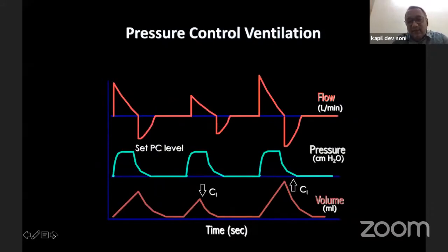Then there can be pressure control ventilation. In pressure control ventilation, you are setting the pressure. The pressures are fixed, what you can achieve in the patient's lung. So the volume and the flow become dependent variables on the lung condition. So you can see the pressure is fixed. This is the flow, inspiration, and then this is the expiration. They can vary. You can see there's a variation in the flow because now these are dependent variables on the lung condition.